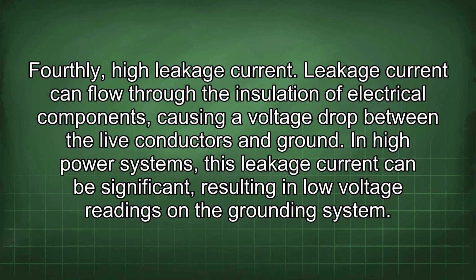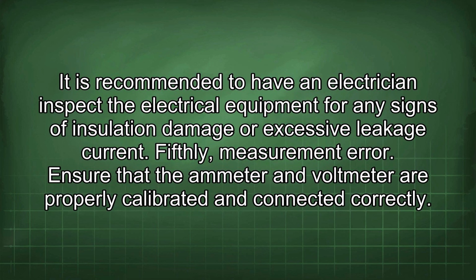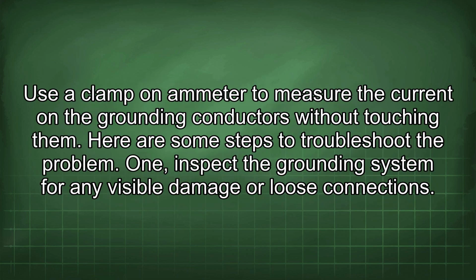Fourthly, high leakage current. Leakage current can flow through the insulation of electrical components, causing a voltage drop between the live conductors and ground. In high-power systems, this leakage current can be significant, resulting in low voltage readings on the grounding system. It is recommended to have an electrician inspect the electrical equipment for any signs of insulation damage or excessive leakage current. Fifthly, measurement error. Ensure that the ammeter and voltmeter are properly calibrated and connected correctly. Use a clamp-on ammeter to measure the current on the grounding conductors without touching them.